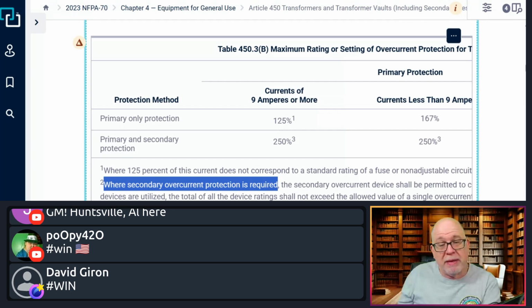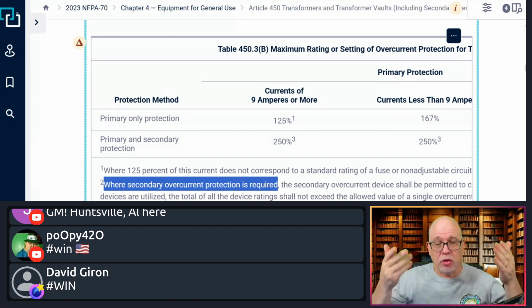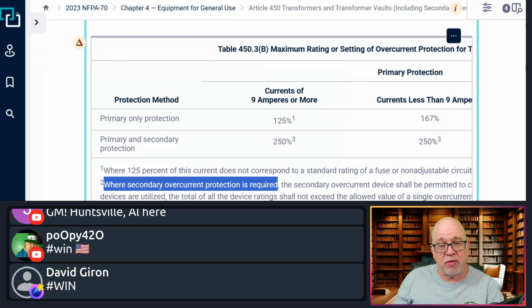And that's going to be most all of your applications, except for what we said when you would do the primary at 125% and then not have any secondary protection. That is very specific applications to meet, and everything has to be met in 240.21(C)(1). All those things have to be strictly met. One voltage, again, 480 primary, 240 secondary, 240 primary, 120 secondary, those types of things. On 3-phase, it's delta-delta. On a single phase, it's just single phase applications, but only one voltage. Otherwise, I'm going to be jumping down into the one where I'm going to have primary and secondary protection. And for most all cases, I'm going to be supplying a panelboard, and that panelboard is going to require some type of protection. So if I have some protection there, then it's going to kick me into having primary and secondary protection.